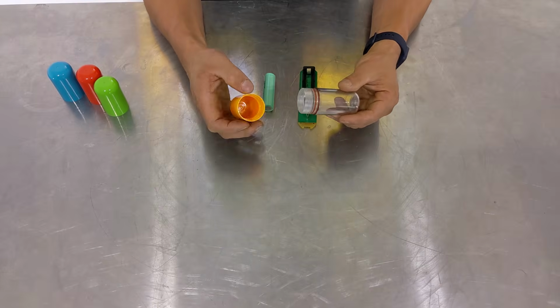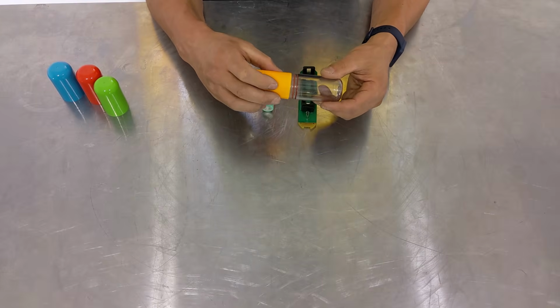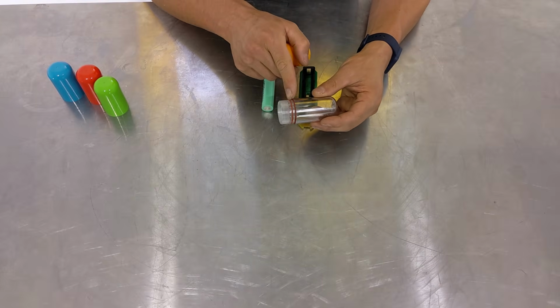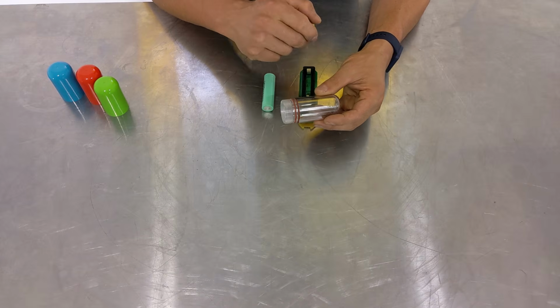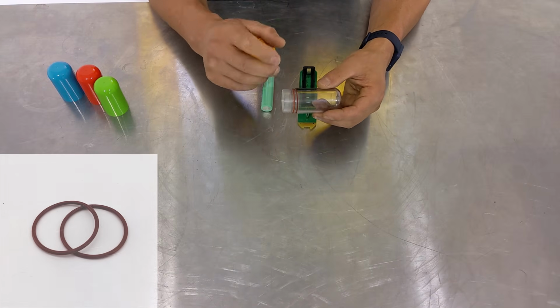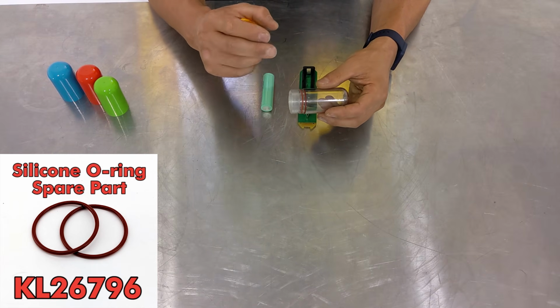However, with this device we have double O-rings, so if you ever take the unit apart and you see a bit of liquid halfway between one O-ring and another, that's a good indication that one of the O-rings needs to be changed over, so don't leave it any longer.